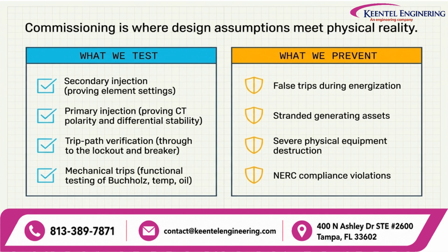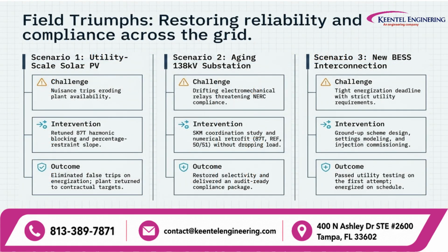The prevention objectives are equally important. Proper commissioning helps prevent false trips during energization, avoids stranded generating assets, reduces the risk of severe physical equipment damage, and helps prevent compliance violations. In other words, commissioning is the final opportunity to identify problems before the transformer becomes operational. Protection engineering becomes especially valuable when applied to real-world operating challenges.